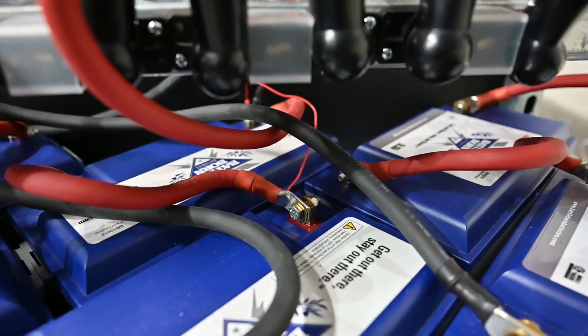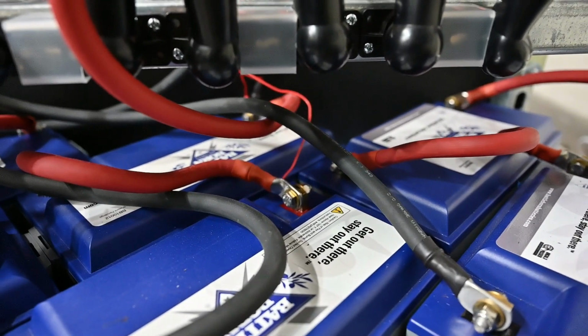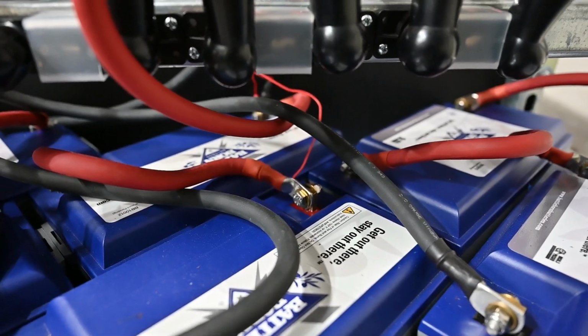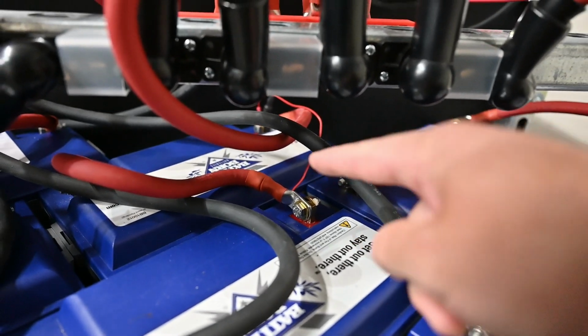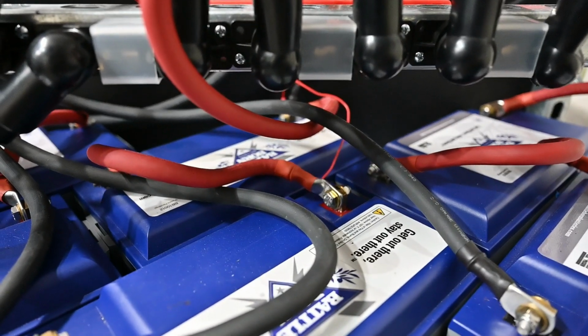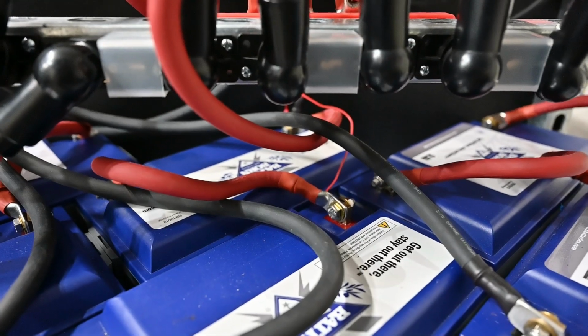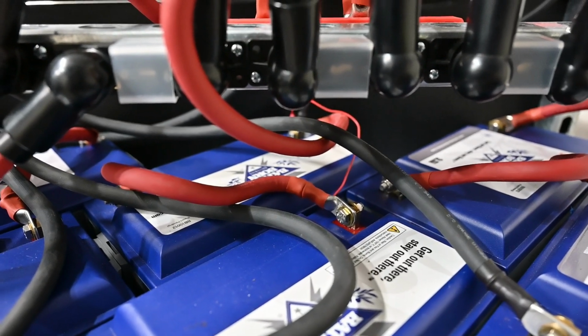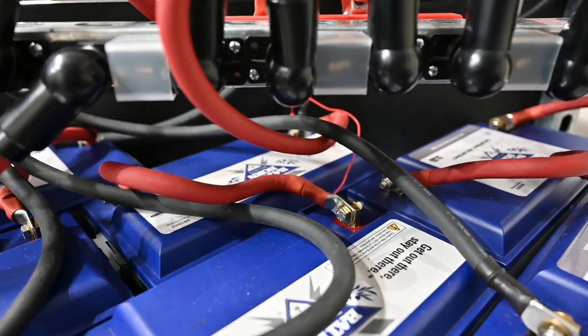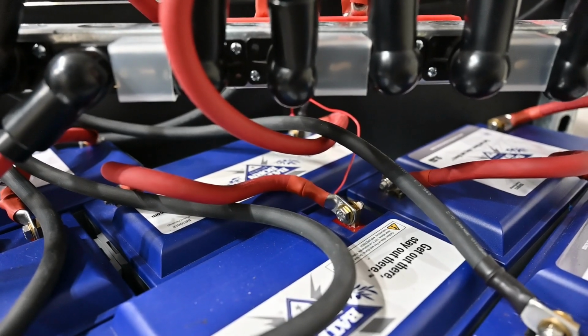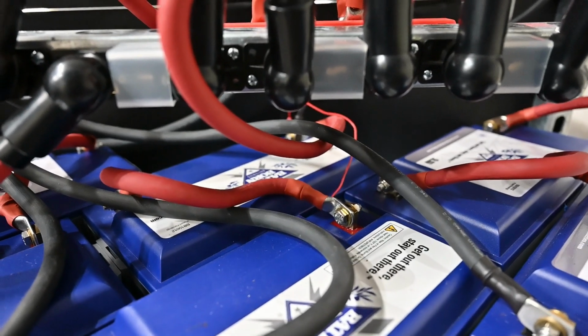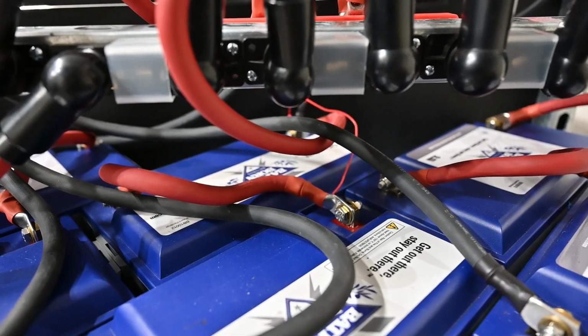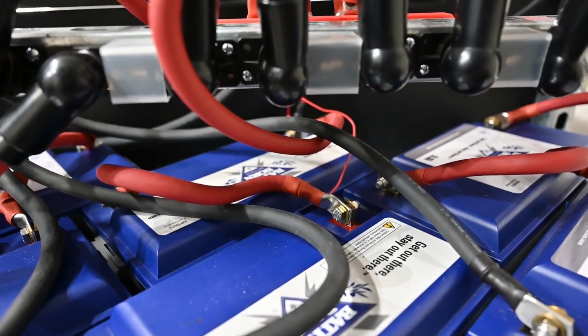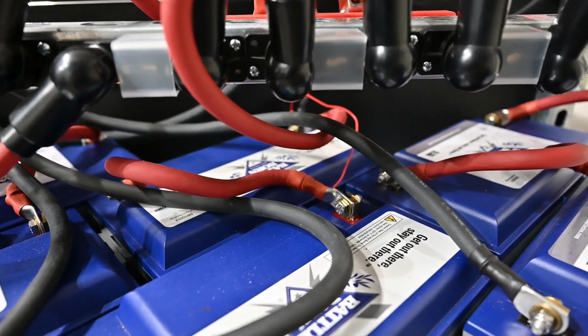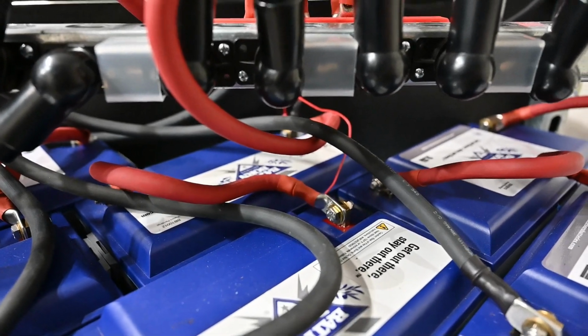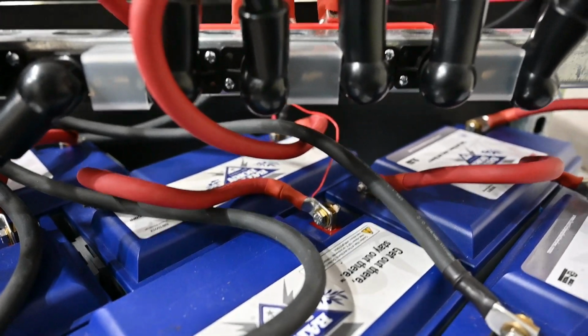An additional cable is connected to what's called the midpoint voltage, right in there. With series connected batteries, there's no guarantee that both batteries are going to be at the same voltage, so you want to monitor that and make sure the batteries are charging and discharging at equal rates. If they aren't, you should take it apart and charge the batteries up to 100% to basically neutralize the voltage across them.